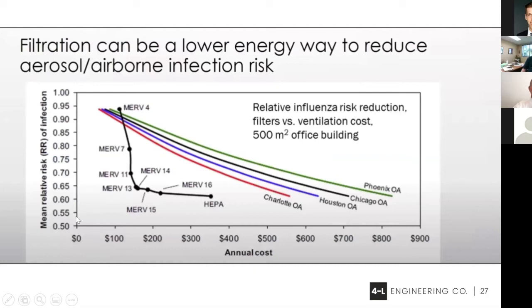Just remember that when we buy these filters, the price is going to go up. So a MERV 4 might only cost us, on an annual cost, somewhere around $125 a year in this example. And when I move to the right to a MERV 13, I'm going to go from $120 there to maybe $150 right there. And so as I go on up, my price goes up. So remember, when we're changing the MERV rating of our filter, we have to first check to see if it'll work, see what one we can do. If we can adapt, we do it, and understand that everything's going to cost more. Next slide.